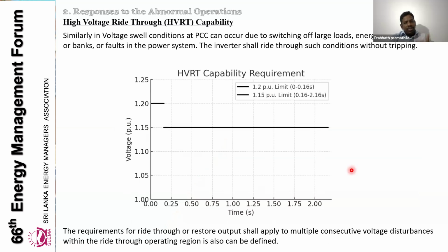Similar to the LVRT on the low voltage side, there is another option to have high voltage ride through as well. If there is any switching of a large load, maybe energizing a capacitor bank, or any fault, the voltage can increase very suddenly, within milliseconds. The inverter should be able to ride through such conditions without tripping. When tripping happens, there are reconnection delays, enter to service delays as well, and these situations can worsen our network stability.